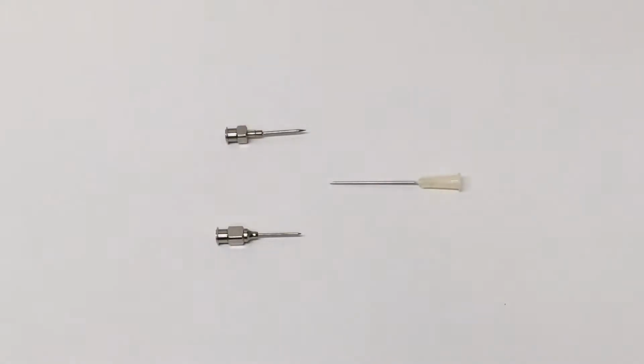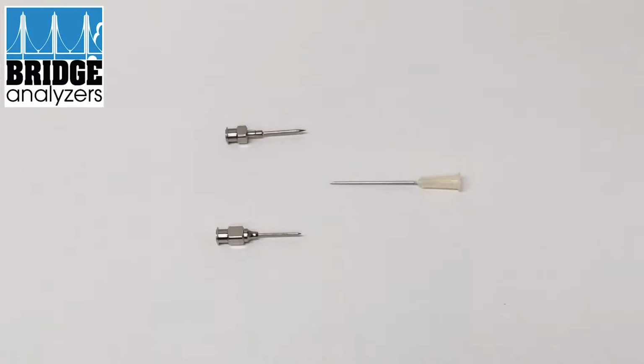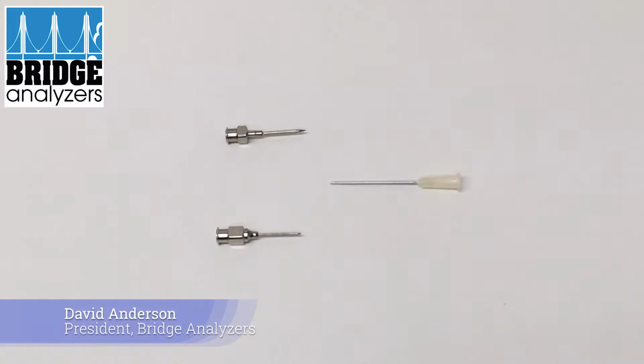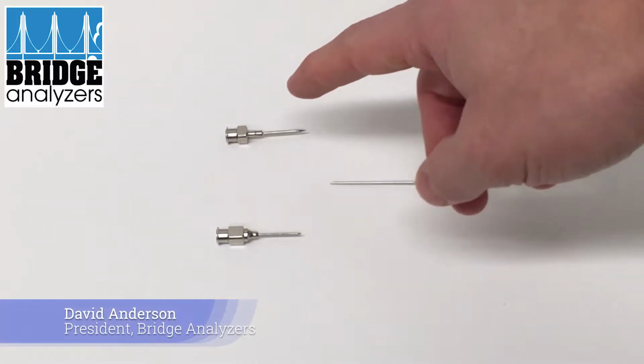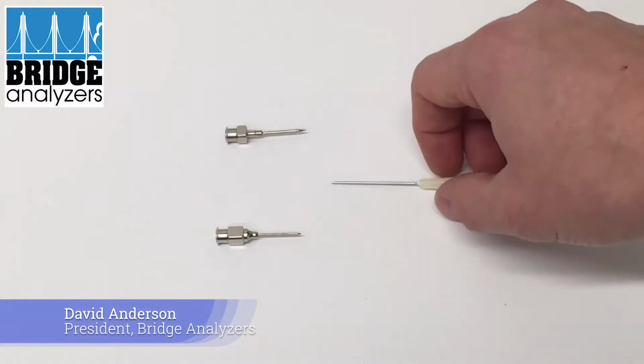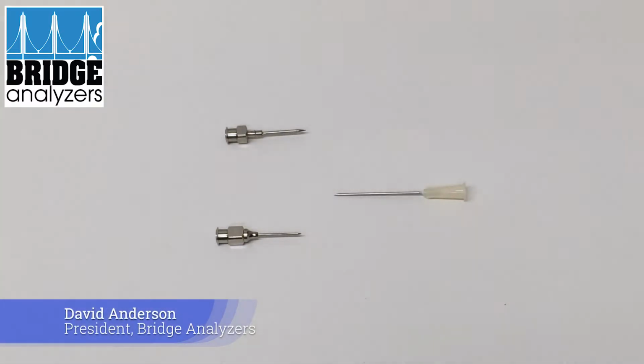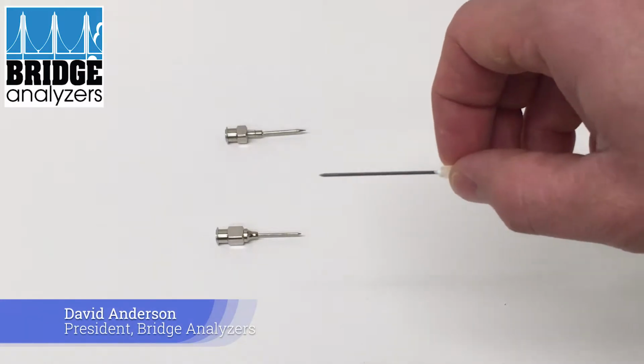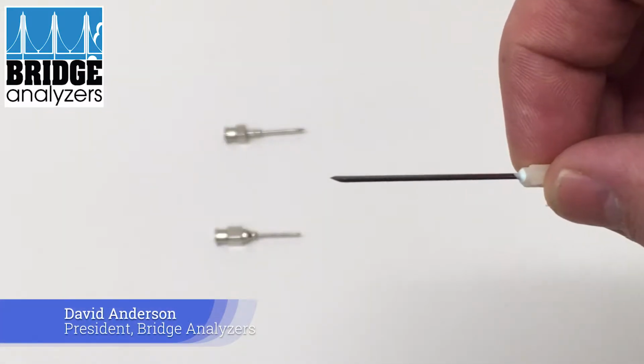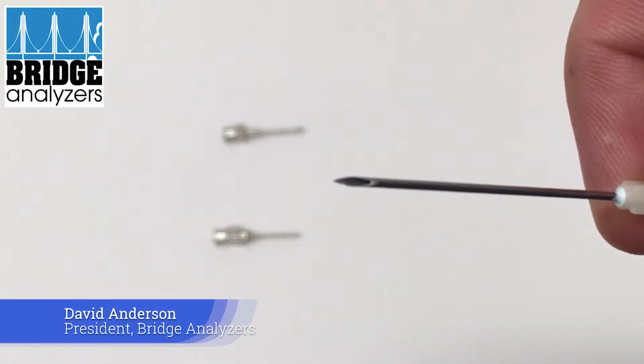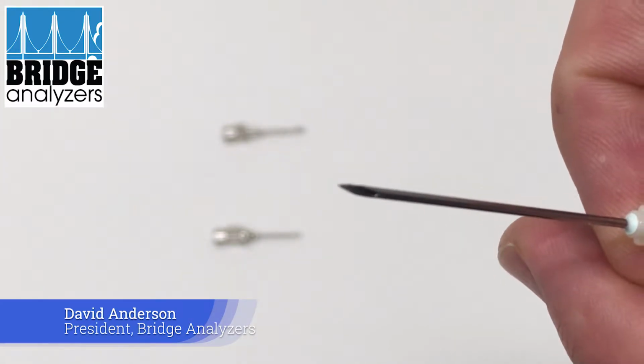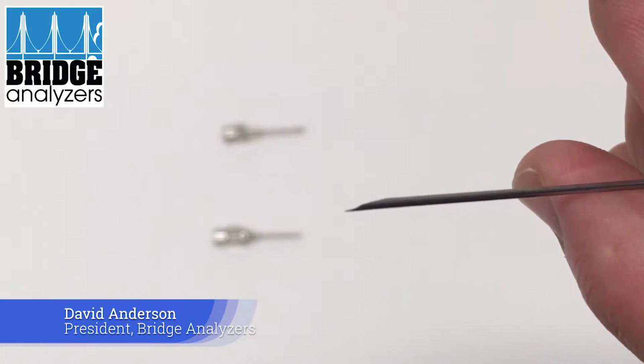So some customers have wondered, why don't we just use a hypodermic needle for MAP gas testing? Well, we've designed two needles specifically to address some of the concerns related to the use of hypodermic needles in MAP testing. If you think about the origins of a hypodermic needle, they're specifically designed to puncture skin and also to inject or draw out liquid. When you're doing MAP gas testing, you really don't want to pierce skin, and you also don't want to ingest or draw in any kind of liquid into the gas analyzer.